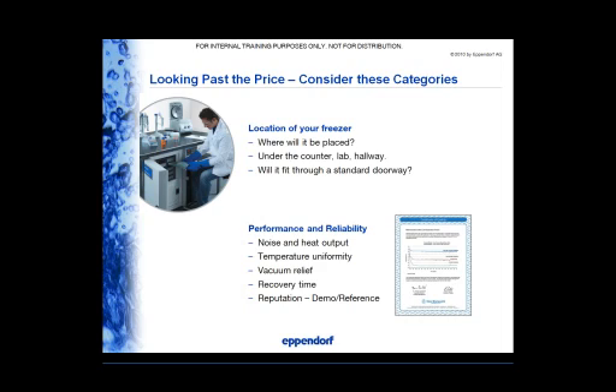Temperature uniformity is pretty much the delta T, or the temperature difference between the lowest and the highest temperature inside your freezer. So it's more of a peace of mind to you, the customer, that when you set your minus 80 Celsius freezer, all your samples will also be at minus 80 degrees Celsius, whether it's on the top shelf or on the bottom shelf.